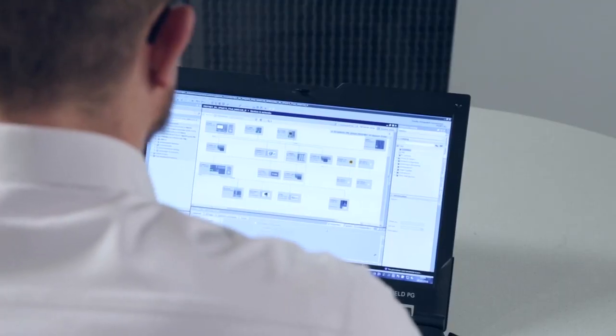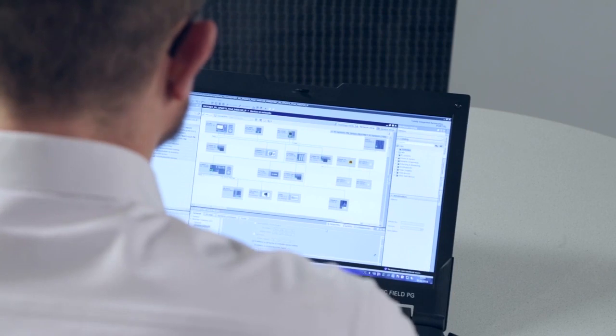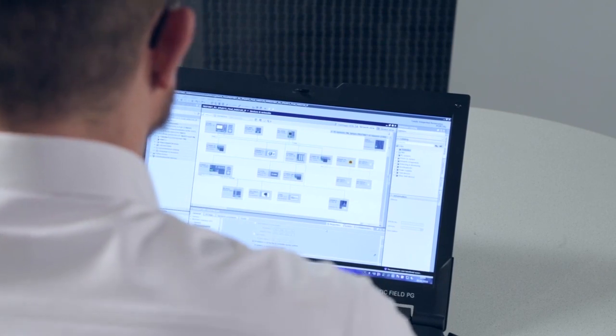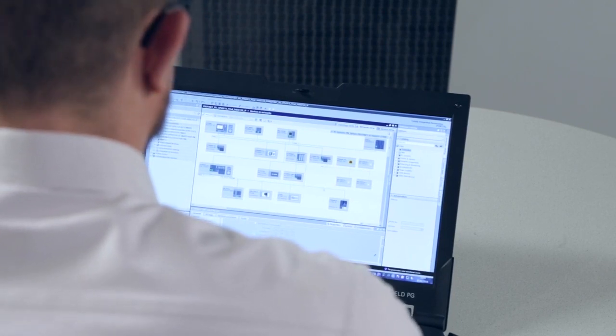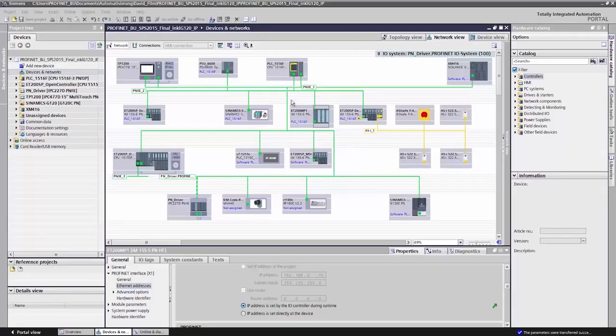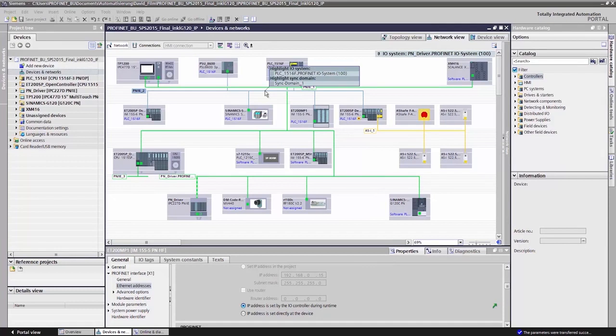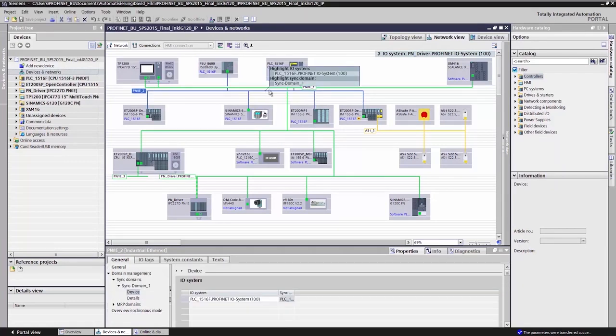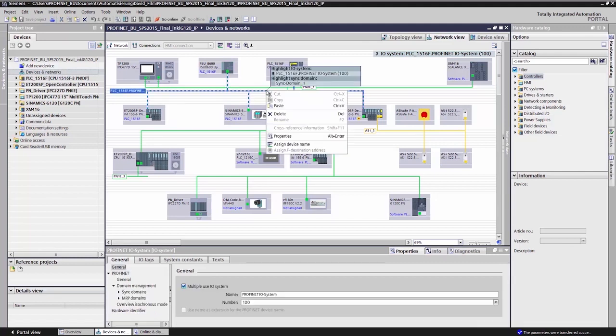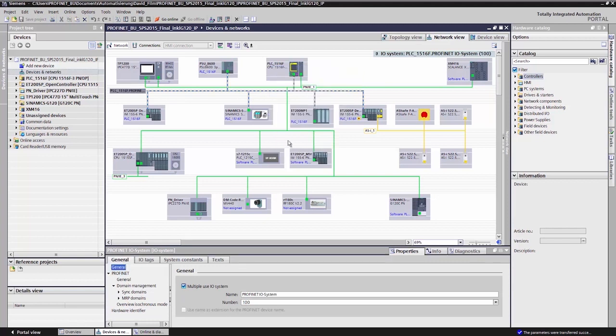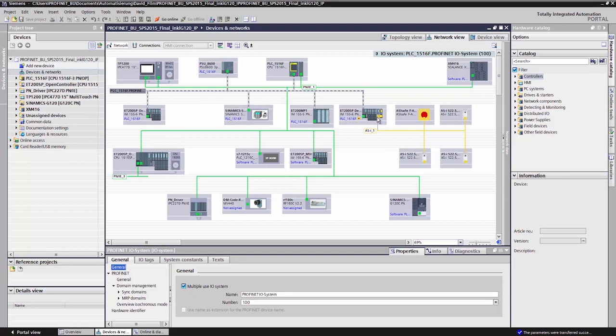To be able to use the automatic addressing feature, I need to implement certain settings in the TIA portal. In the device and network view, I mark the PLC's I/O system. The highlighted dashed line shows the I/O system. I right-click on properties. And check multiple use I/O system. In doing this, I grant the TIA portal permission for the CPU to overwrite all IP addresses of the assigned I/O devices.